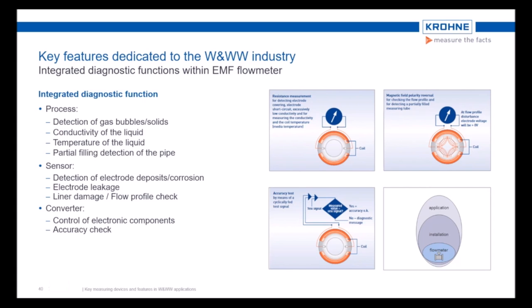Depending on the converter type, the device will provide you such information as detection of gas bubbles, electrode corrosion or coatings, as well as liner damages. The device can also check if it is still running within the given accuracy ranges and if the flow profile is still good enough. All additional parameters can be transmitted by several output communications, such as analog or digital, by Profinet, Profibus or Modbus.